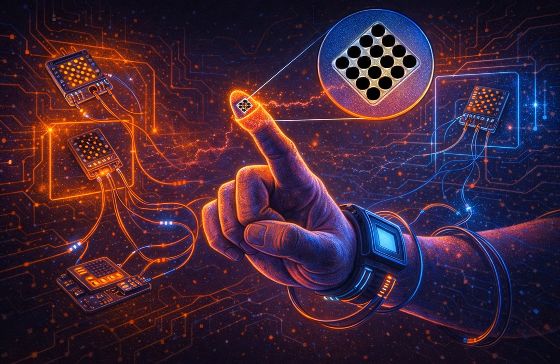It also enables real-time exploration. You get UI sliders that let you dynamically adjust all the pulse parameters, amplitude, pulse width, frequency, while the device is running, facilitating rapid experimentation. It does. And for validation, it has a click and sense feature to activate individual electrodes. The GUI also gives you a real-time visualization of activated electrodes and, crucially, impedance readings to check the quality of skin contact. So what does this all mean for the design community?